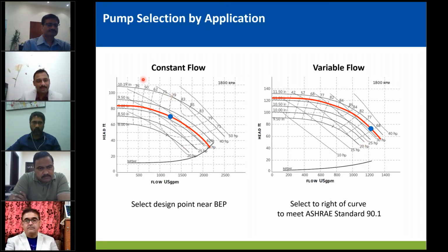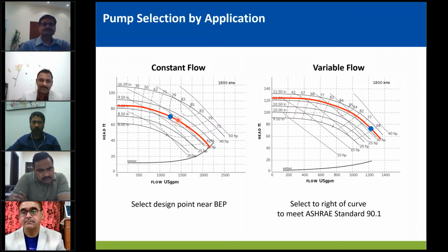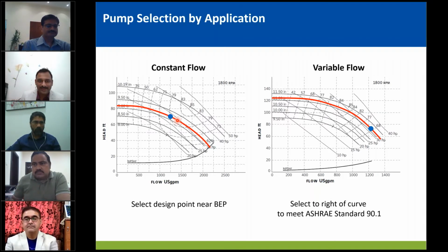Now when we have the constant flow pump on the left hand side, we are used to selecting the pump closest to the best efficiency point, preferably slightly left hand side of the BEP point. So even if the system head is less, it comes out there and operates and falls into the best efficiency area. This is still a good practice when there's no variable speed drive on it, and you know that you're slightly oversizing the pump head, which is the case most of the time.